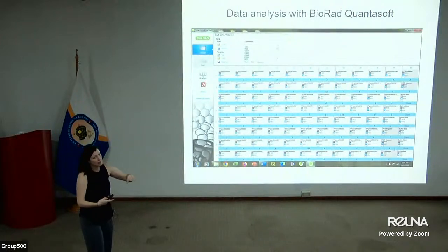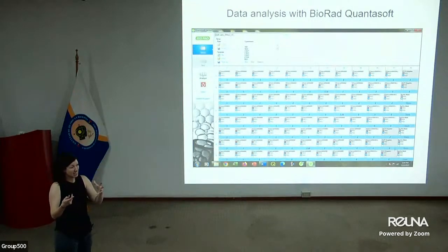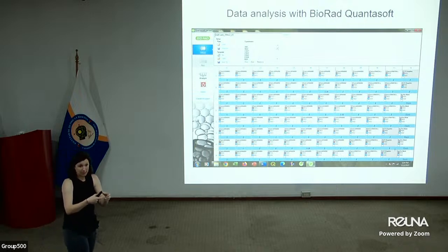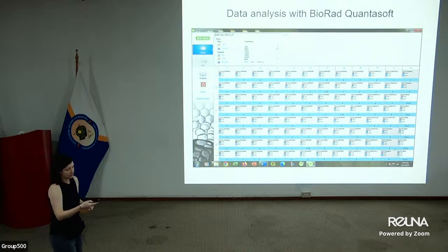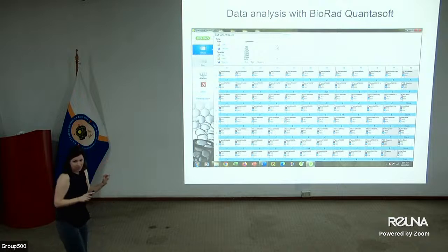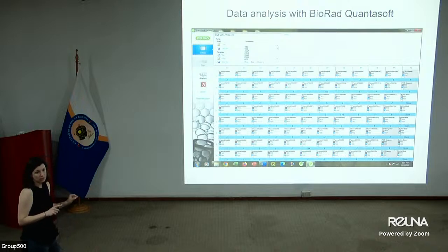And so what it does, and this makes it really different from qPCR, is it'll pull the sample and then it counts the droplets. This entire process for a plate takes 3.5 hours. Counts the droplets, but this is the key. It discards the sample. So you don't have anything left over. After your sample is read, you just have an empty plate. So it actually destroys the sample that you have, which is a con because you can't sequence it. That's why assay development is everything. You have to be overly rigorous with your assay development with ddPCR compared to qPCR, where you can just sequence it.